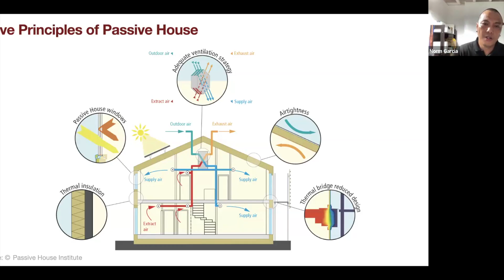And passive house, this is a performance standard. So there are very strict criteria for hot and humid climates. It sets a maximum limit of 15 kilowatt hours per square meter per year, plus a variable allowance for cooling and dehumidification. And for the cooling load, it's very strict. The cooling load needs to be no more than 10 watts per square meter. And air tightness for new construction is 0.6 air changes per hour. For retrofits, slightly relaxed at 1. And for frequency of overheating, the interior of the building should not exceed 25 Celsius for more than 10% of the time without active cooling. And if there's active cooling, then the active cooling equipment should be adequately sized.